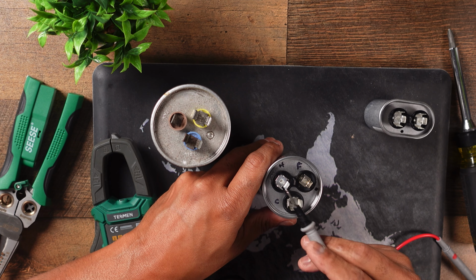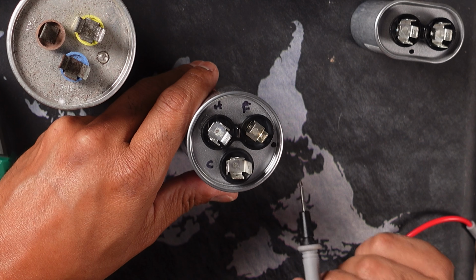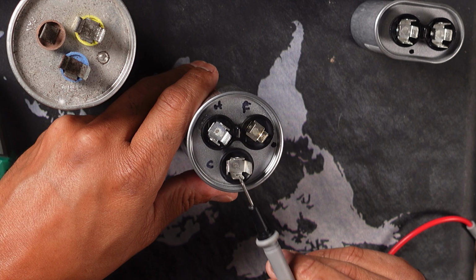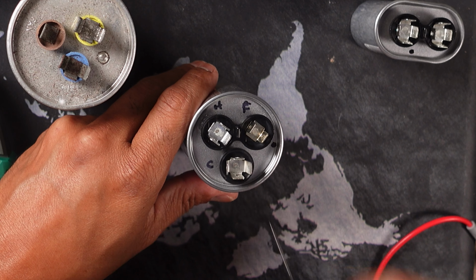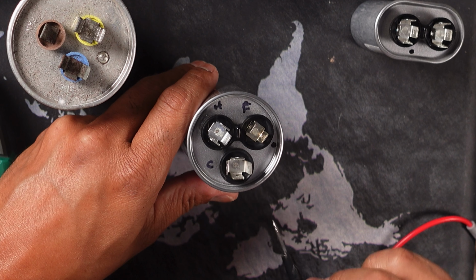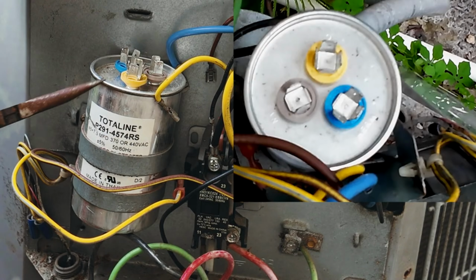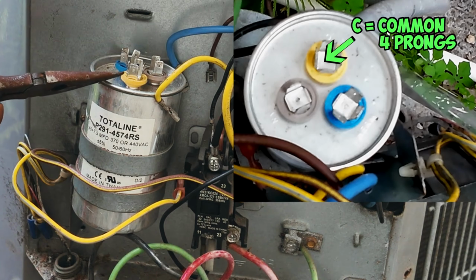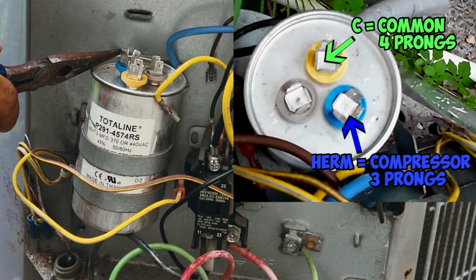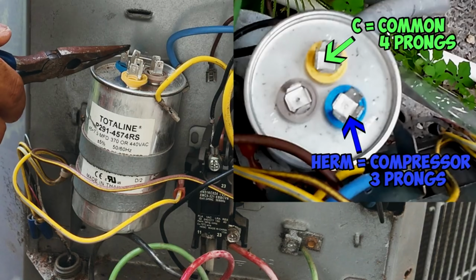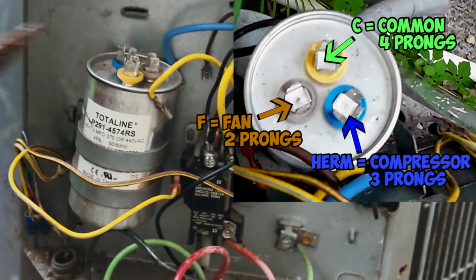Now, if you don't have any labels on your capacitor, the first thing I want you to do is take note of the amount of terminals that are on your capacitor. If you notice, this one has the most, which is 4. Your common will always have the most terminals. The port with the second most terminals is going to be your compressor, and lastly, the one with the least amount of terminals is going to be your fan.